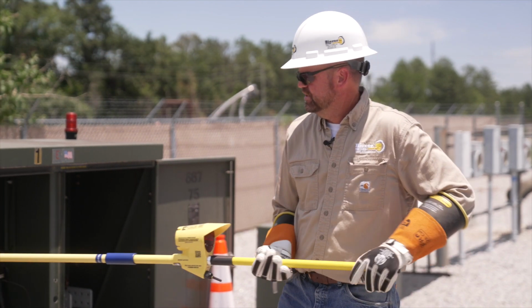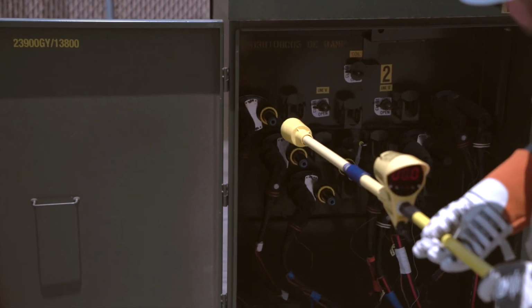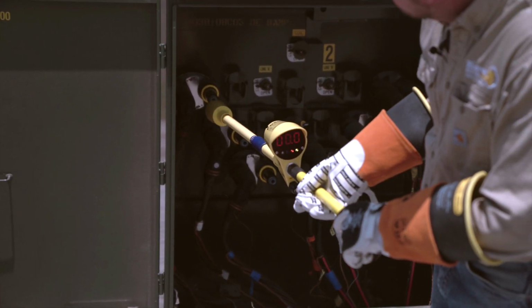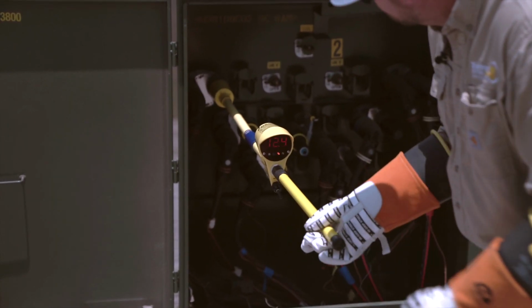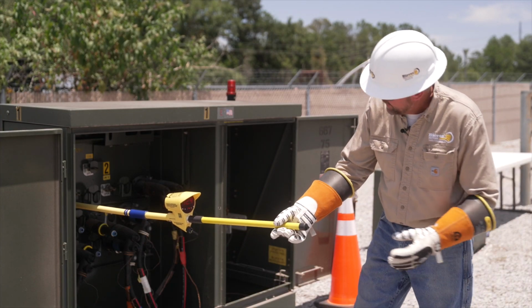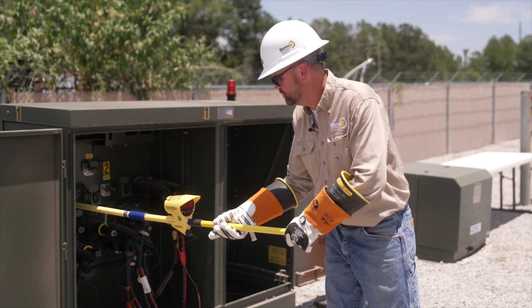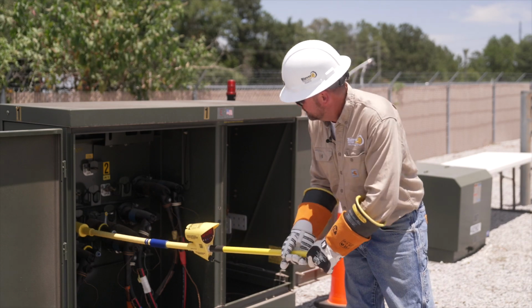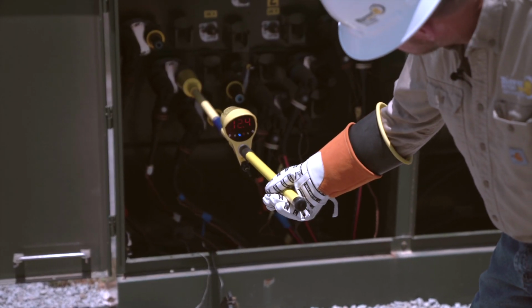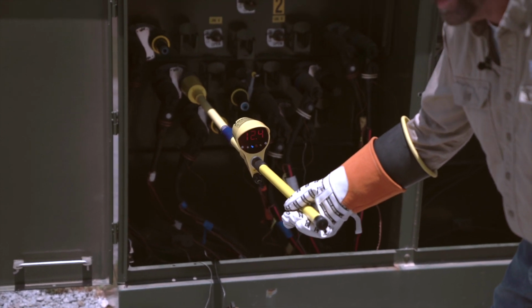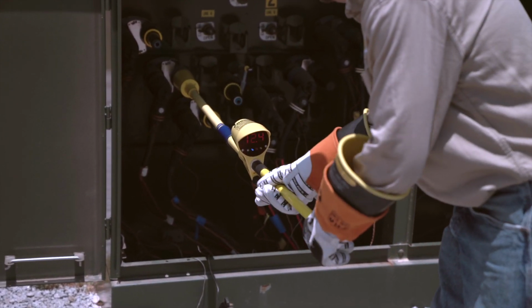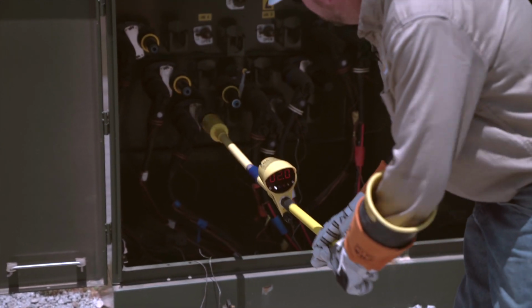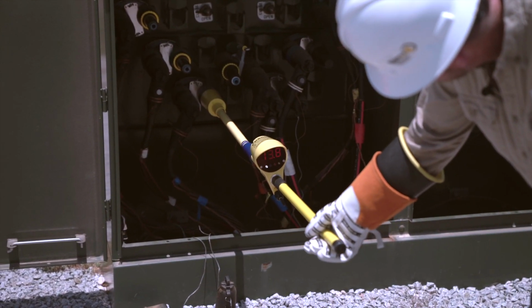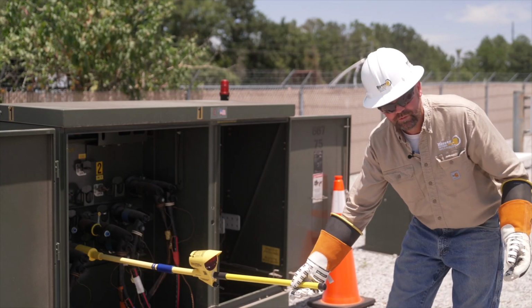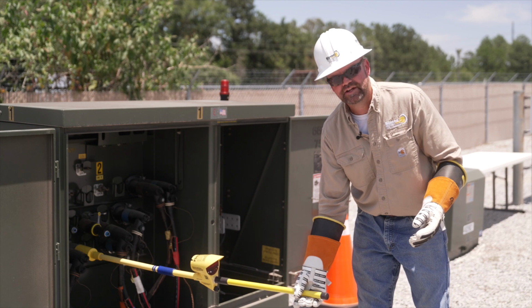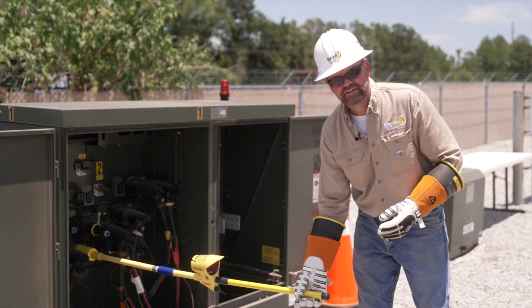So I'll start with the top bushing first. You'll notice before I even insert it into the bushing, I get a red light. So I know this is my 240 degrees. It's not in phase with my reference probe. And I'm getting about 12.5 kV. So that's my nominal voltage reading. The H2A bushing, again I have about 12.5 kV, a blue light. This is not where my reference probe is attached. And my H3A bushing, I have my white light, about 13.8 kV. So that's my nominal voltage reading phase to ground. Again, it's much more accurate. In this case, it's within 1% of true RMS.